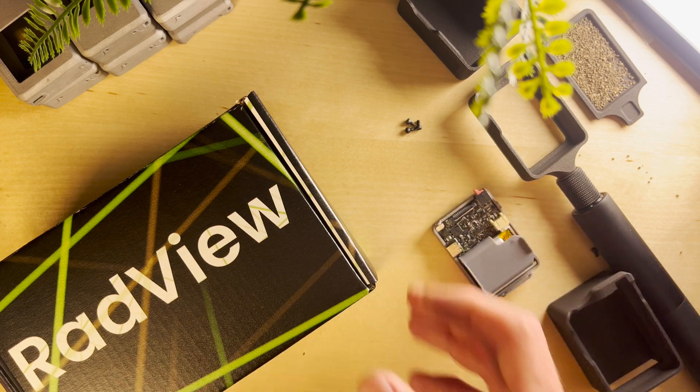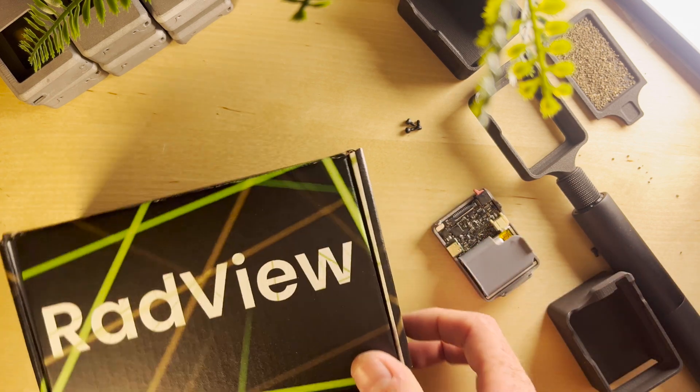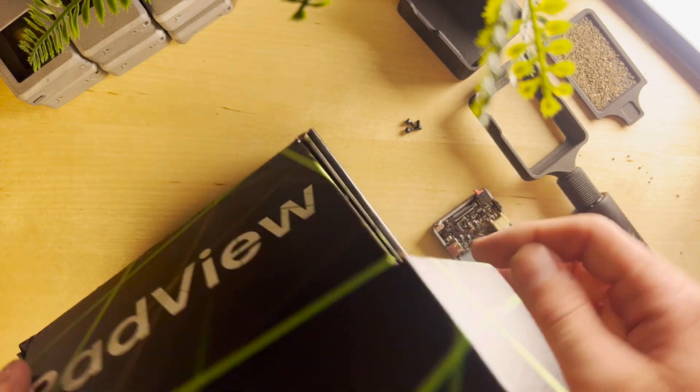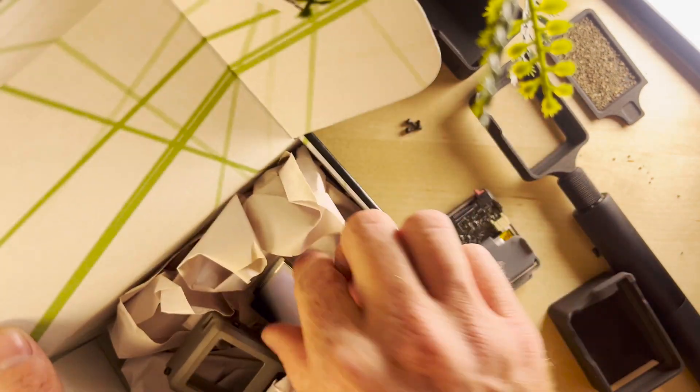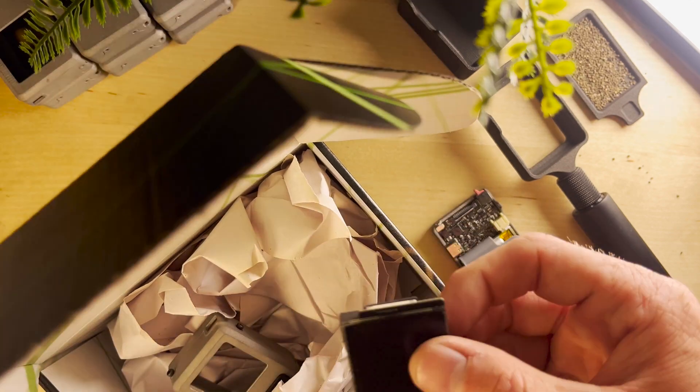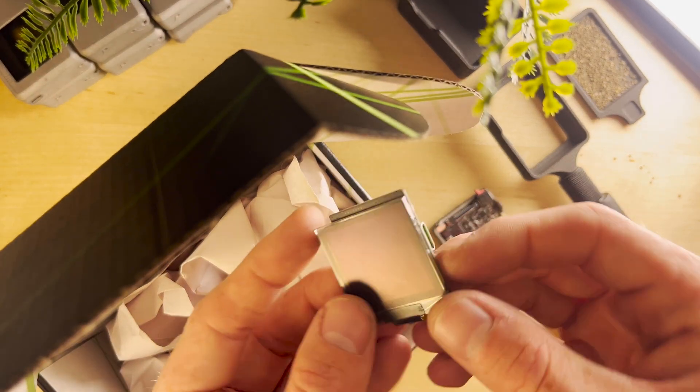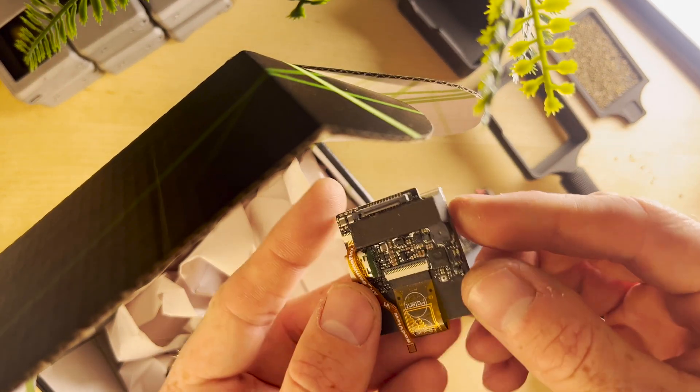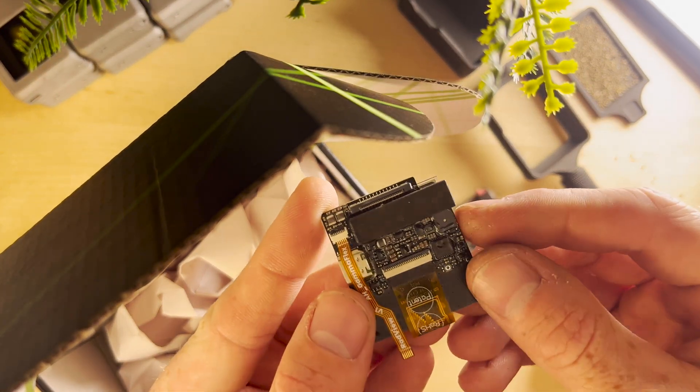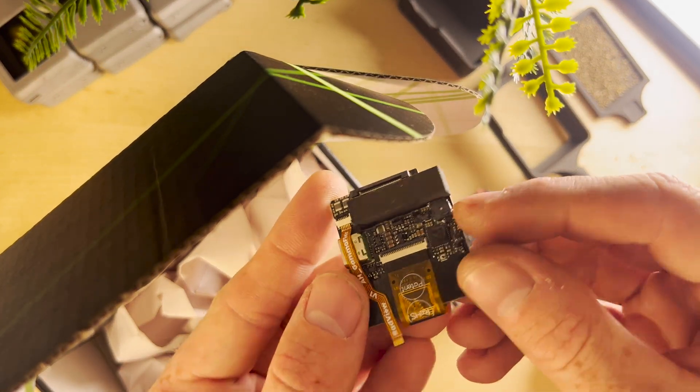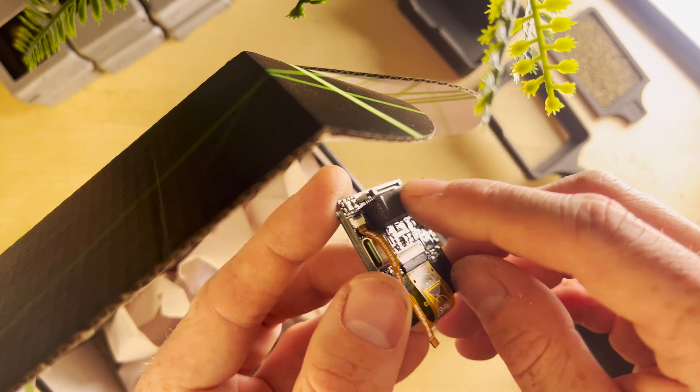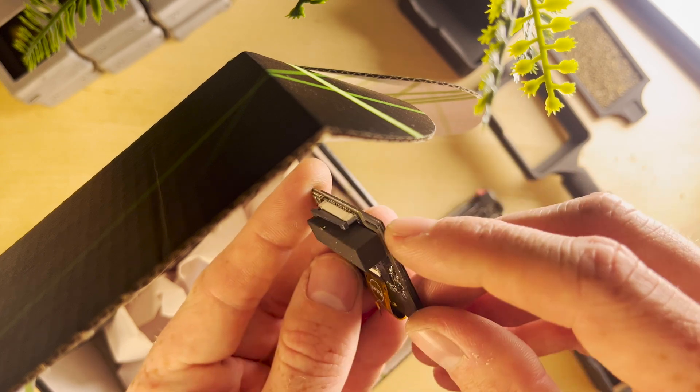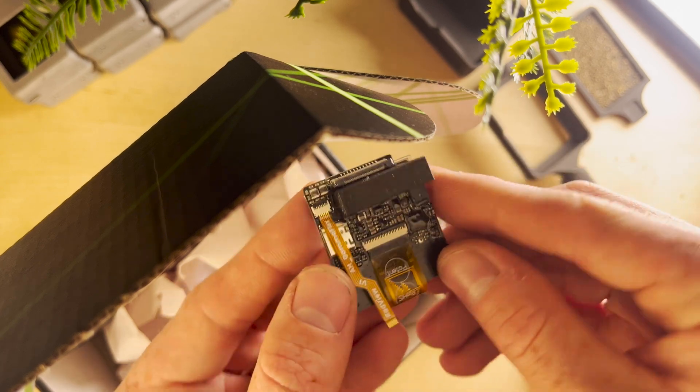Next up we're going to grab our Gamma Mod. They ship like this and we have our Gamma Mod piece right here. It's actually attached to the back of the display. You can see here we have all the chips needed and our BGO scintillator up top there.